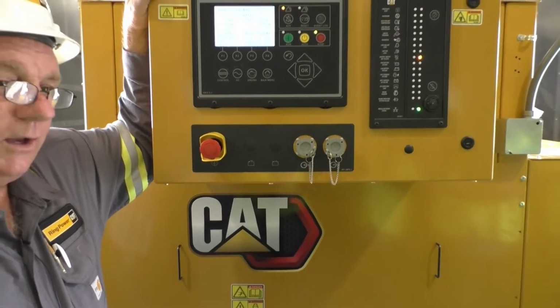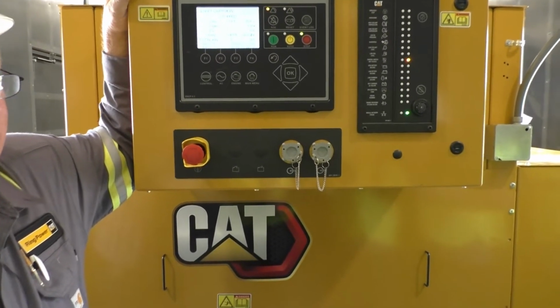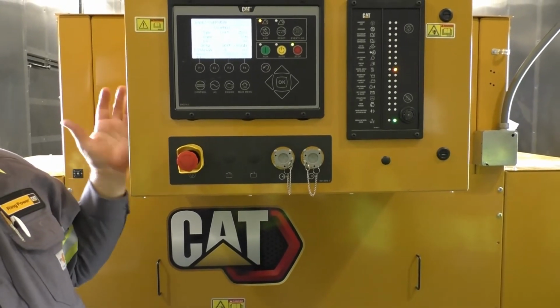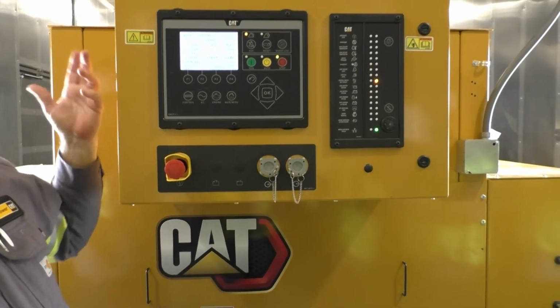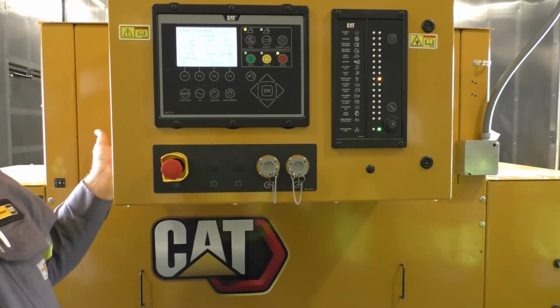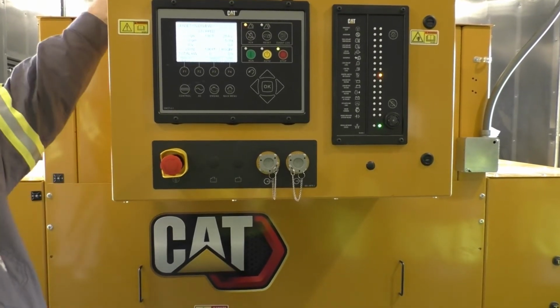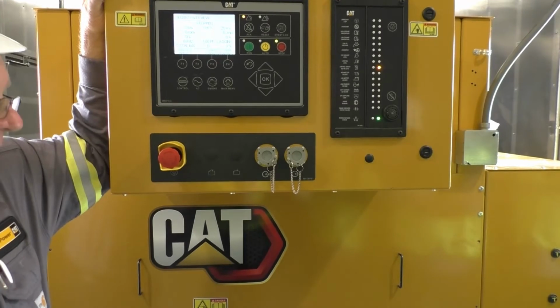Well, it's a white building, so that helps. But it's not even the building. It's after you run this and you shut it down. What's going to happen? It's going to heat soak the room. The engine fan's no longer running, so you're not going to cool it that way. The only other way to get the heat out of the room is that fan.